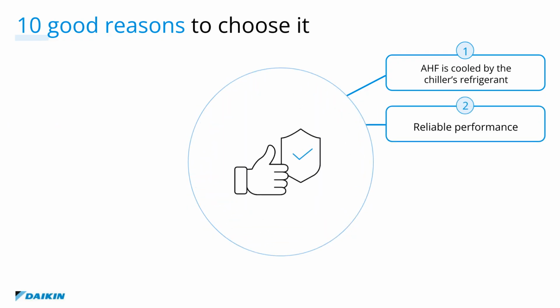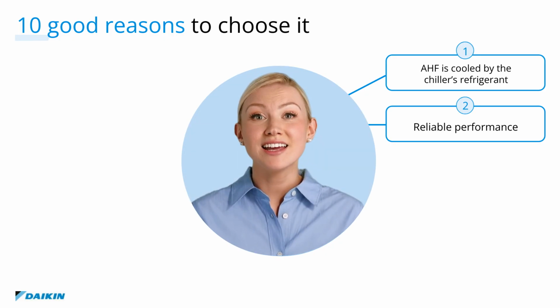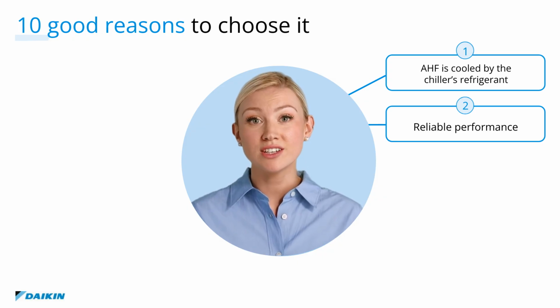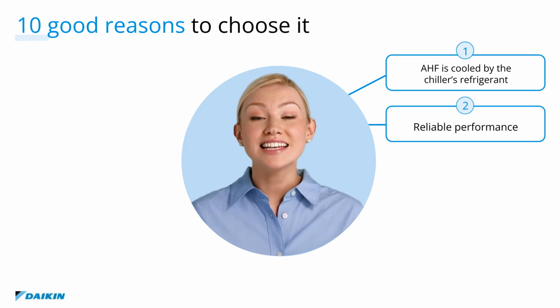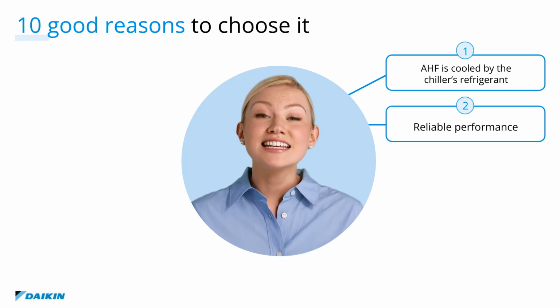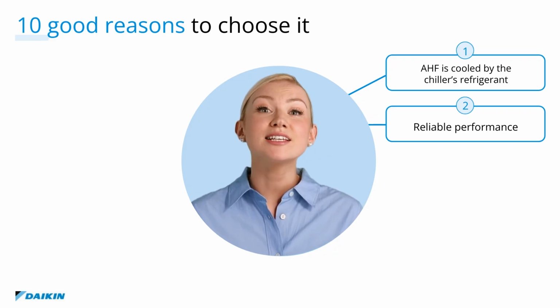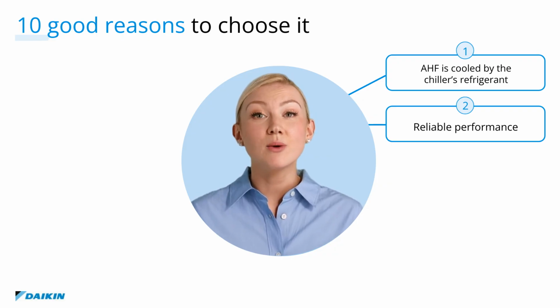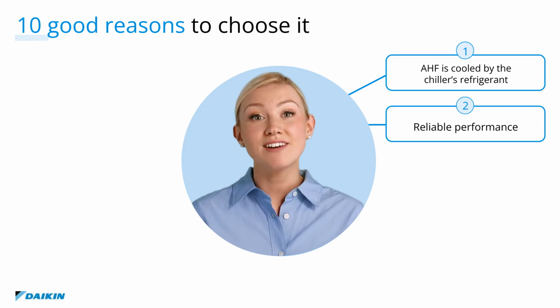Now, turning to performance, the AHF ensures reliable operation even in extreme conditions, thanks to its robust thermal management system, which keeps the electronics within safe operating limits. Its refrigerant-based cooling design maintains low internal temperatures, reducing stress on components and extending their lifespan. With no fans to fail and no filters to clog, the risk of breakdown is significantly reduced, and there is no need for scheduled filter maintenance, an important advantage for data centers operating around the clock.